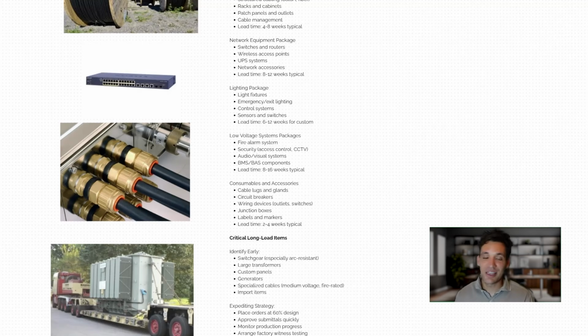So in practice, you place all your orders for the long lead time electrical equipment at the 60% design stage, and you just need to approve the shop drawings quickly, keep the ball moving, manage the contract, and make sure that you're coordinating all the factory acceptance testing, just to move the process along as fast as possible, because no project I've ever worked on has had tons of time to order this equipment. It just takes so long to come. So the key issue with electrical procurement is managing lead times.